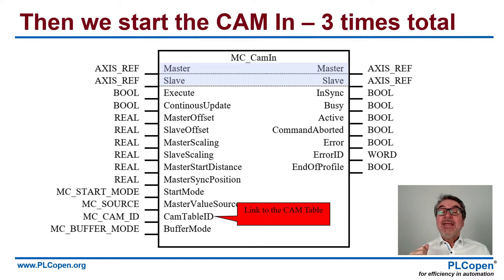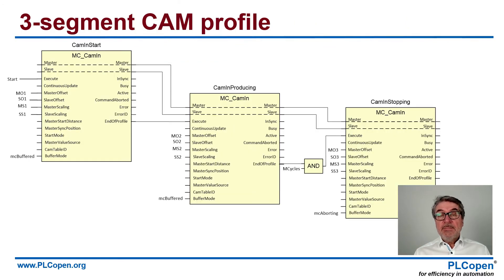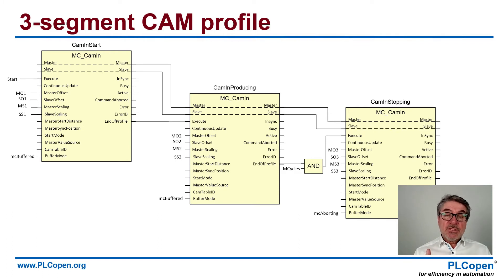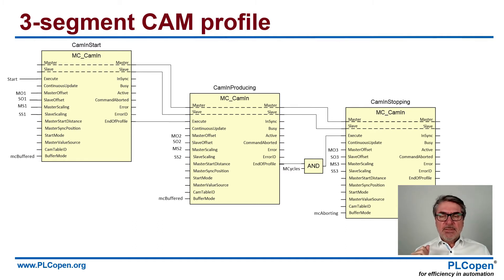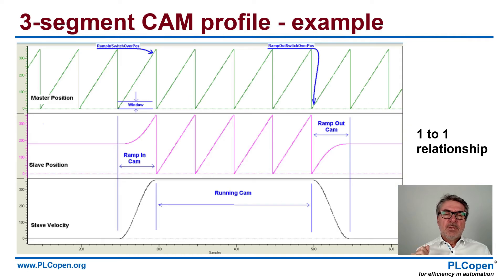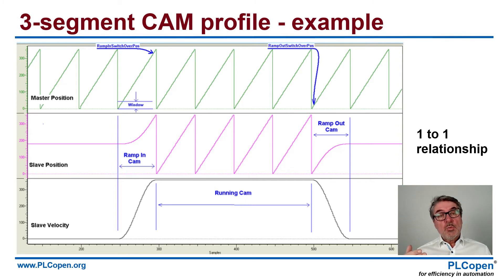We get the link to the CAM table ID coming in from the previous function block. We used it three times in this case to create this profile — you see the CAM_In start, CAM_In producing, and the CAM_In stopping. We use three instances; we could use it with one, but it makes the program unclear. Here you see this link between the master and the slave, which is in a one-to-one relationship.